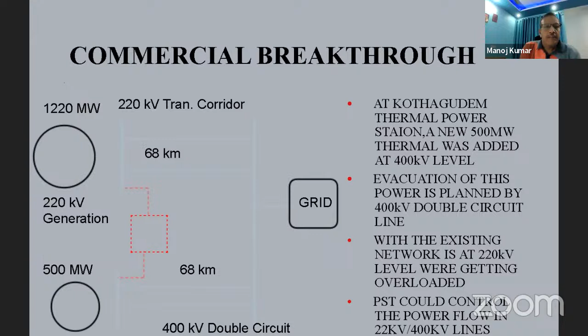However, the 220 kV lines were overloaded and the 400 kV lines were underloaded. So it was planned to put a transformer between the 220 kV bus and the 400 kV bus. Based on the system studies, power was being transferred from the 400 kV side to the 220 kV side, which was not desirable.